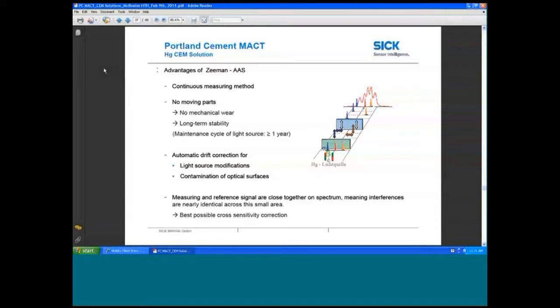What the advantage of this is, of course, it's a very continuous measurement. It gives very quick response. More importantly, relative to even our old mercury analyzer, it's no moving parts, very low maintenance over long periods of time, and very stable. The fact that we're using a single light source through a common set of optics also means that any contamination of the optical surfaces or any degradation of the light source affects both the reference and measurement equally, and it allows us to give a quick correction for that optically. Next slide.